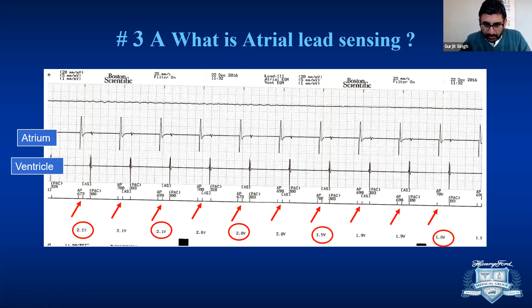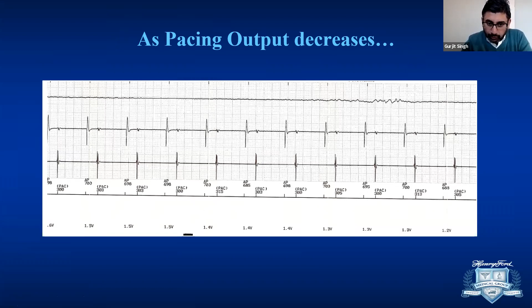So I'm going to make it easy for you. And then we're going to go next. And then here, if you look, as the pacing output is going down to 1.5, 1.4, that middle signal is gone. You still have the far field signal from the ventricular channel. So what that extra signal is, it's some kind of sensing. So what kind of sensing is that? It's called a polarization artifact. It's not that common to see this, but it happens whenever you pace a lead at a higher output.